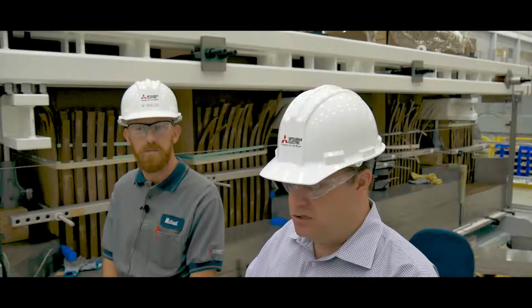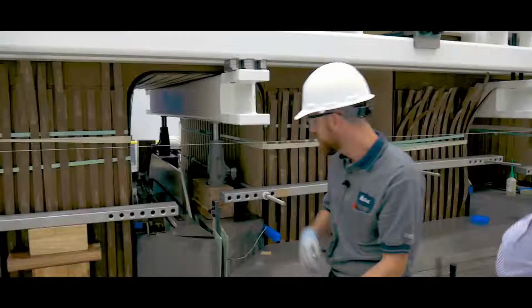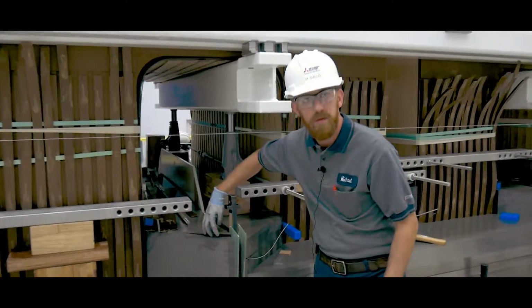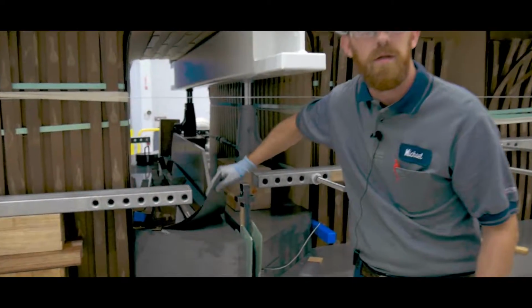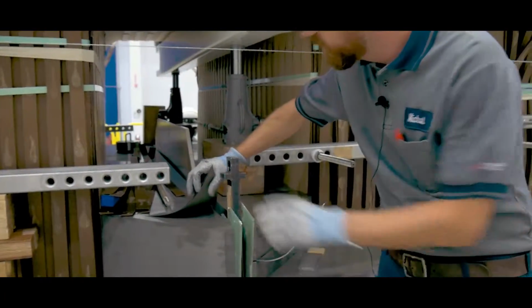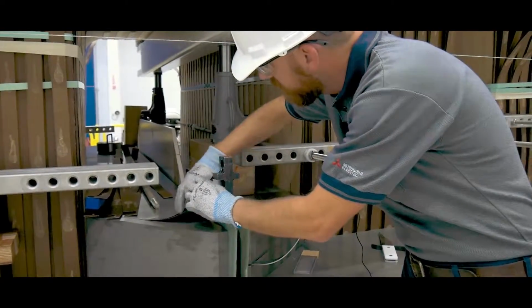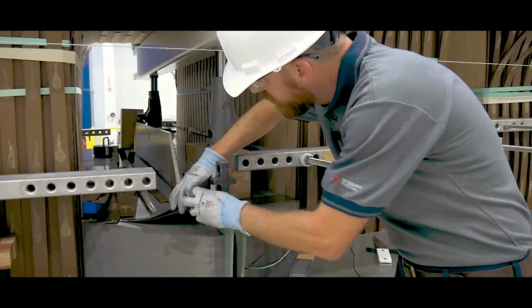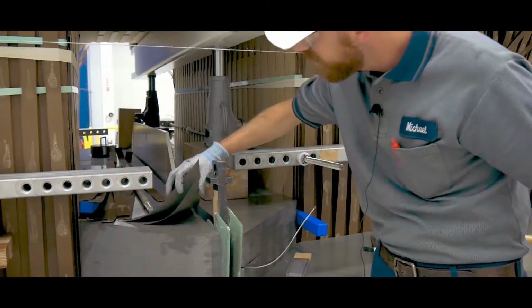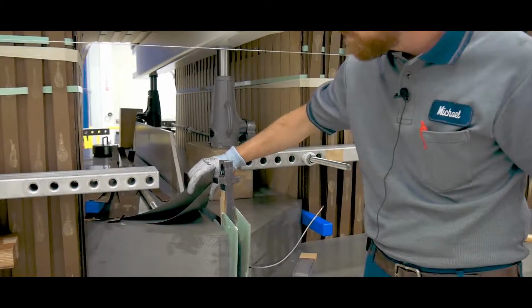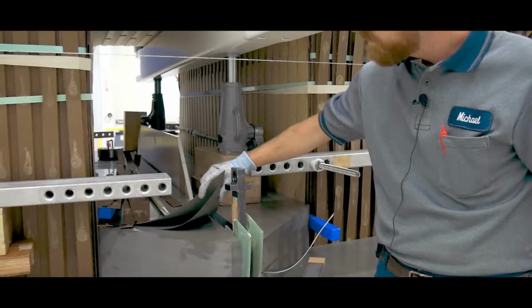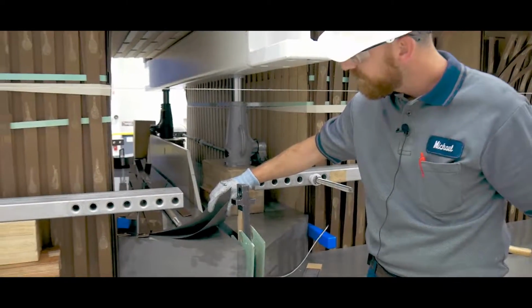The main reason we use so many sheets of steel when stacking the core is to improve the efficiency of the transformer in operation. The thinner sheets are individually insulated from each other with a very thin film, and this insulation allows for low heating of the core steel in the magnetic field, which reduces operating temperatures and minimizes the stray losses of the transformer in service, thereby improving its efficiency.